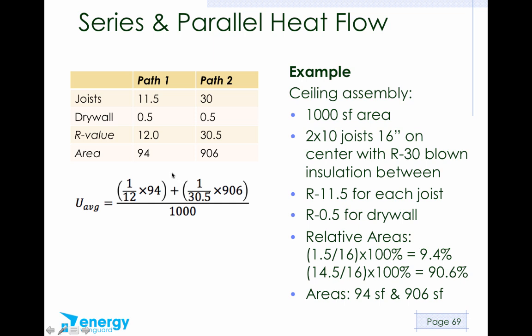Here's our equation now. The average U value is U1 times A1. So U1 is 1 over R12, and the area is 94. U2 is 1 over 30.5, and area 2 is 906. So if we work that out, 94 divided by 12, remember that little shortcut there, is 7.83. And 906 divided by 30.5 is 29.7.